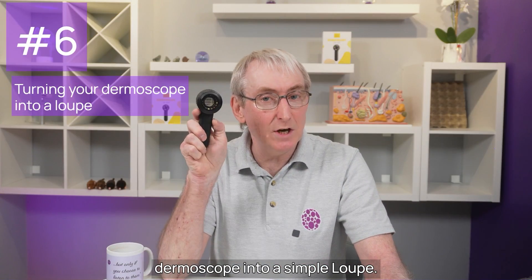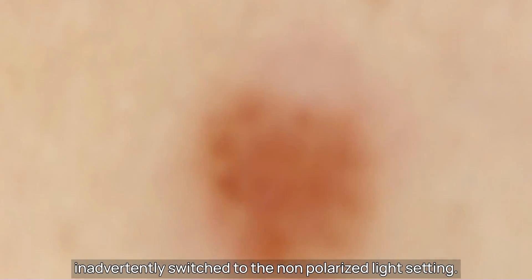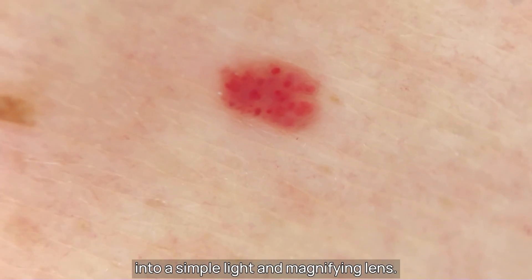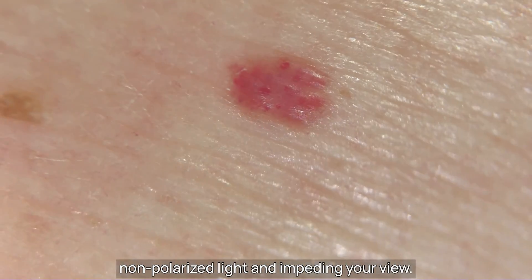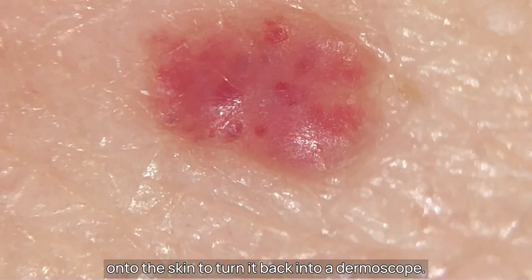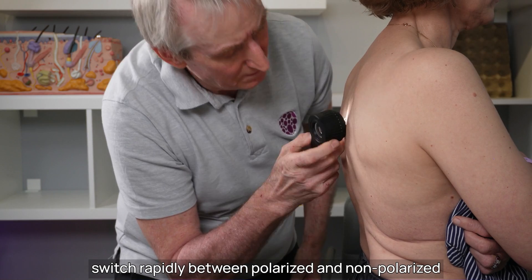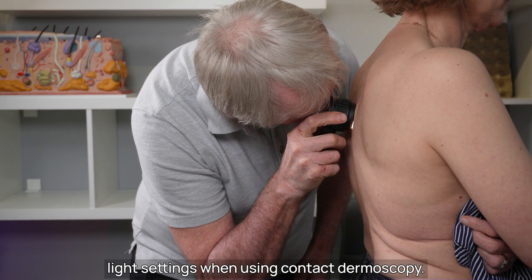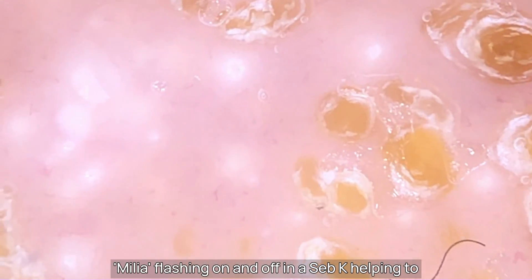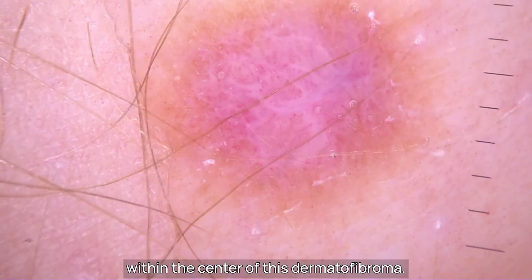Mistake number six: turning your dermoscope into a simple loupe. When using polarised non-contact dermoscopy, you inadvertently switch to the non-polarised light setting. Congratulations — you've just turned your expensive dermoscope into a simple light and magnifying lens. The stratum corneum is now scattering the non-polarised light and impeding your view. Either switch back to the polarised settings, or extend that face plate with a contact medium onto the skin to turn it back into a dermoscope. The advantage of a hybrid dermoscope is being able to switch rapidly between polarised and non-polarised light settings when using contact dermoscopy — but this only works using contact dermoscopy. Then you can get images showing milia flashing on and off in a Seb-K, helping to confirm its benign nature, or shiny white structures within the centre of a dermatofibroma.